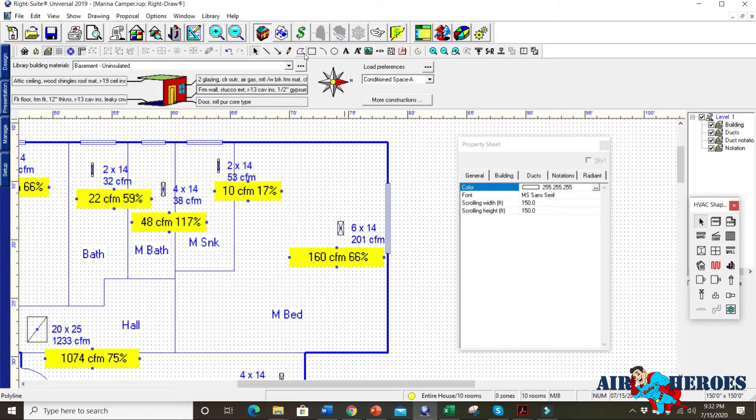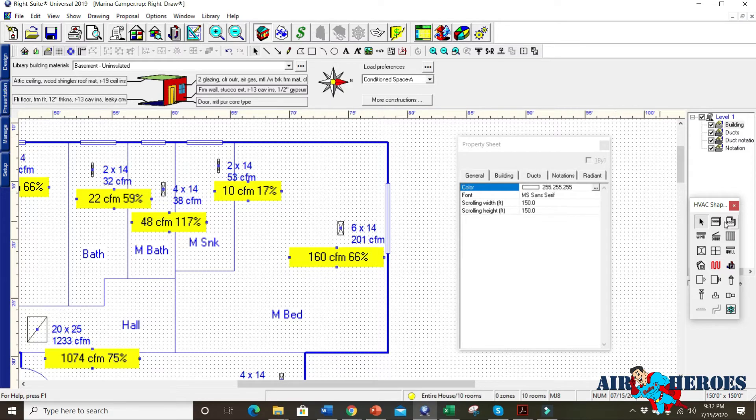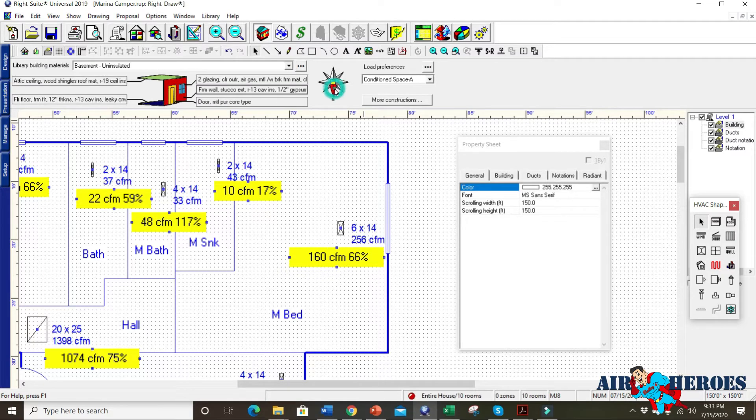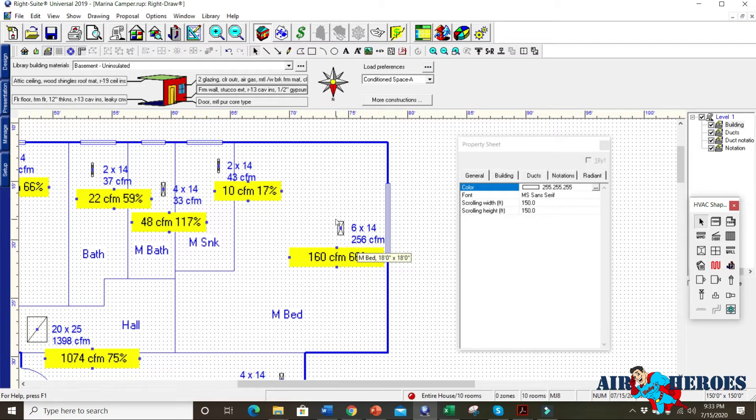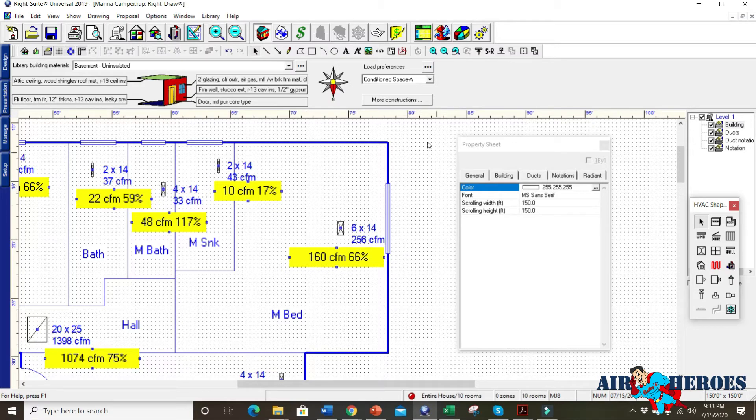If we take and notice how the house, the north is facing this way. If we were to rotate this house to a different direction, watch how the CFM changes. Now we're at 256 CFM down here from 201. And that's just by rotating the house. So this is why rules of thumb don't work. The software model is exactly what it's supposed to be.